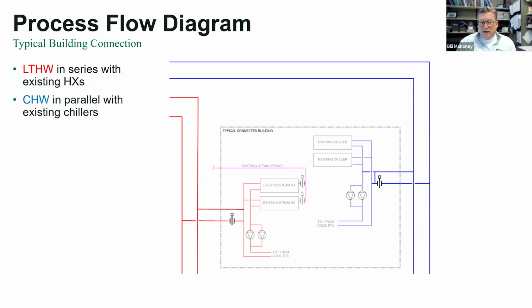Same for the steam system that ties in, except we did go in series on the steam here. We connect into the supply in, and then the return after that. So water flow is going that way. Sorry, return first and then supply. So we basically are running in parallel with the steam heat exchanger or the chiller. That helps with the phasing, because this wasn't all going to happen in one day. So you can go back and forth, do some testing, make changes, go back to your old chiller locally, and it allowed them, a couple years if they wanted to, of transition back and forth until they got the whole new system up and running.